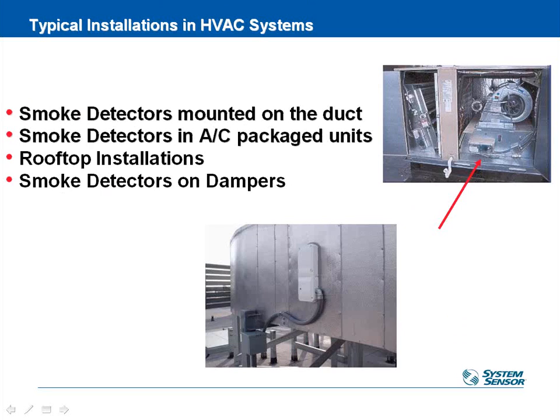You can mount them inside the building, which is preferred. You can mount them outside the building, like this drawing on the bottom shows, but that would be specifically for a weather-tight version of a smoke detector. So not every detector will do that. Just weather-tight versions, NEMA 4 rated. You can mount them inside the package units, inside a rooftop, and we'll talk about how you can do that.